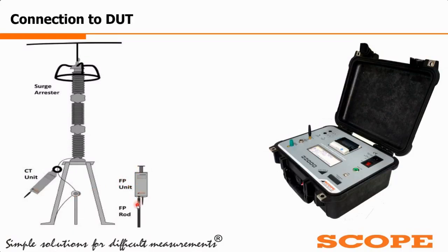The field probe unit with the FRP rod is supplied by default with the FRP rod, and as per your ordering, whether it is for 400 kV, 220 kV or 765 kV, we give the appropriate length of rod. But still, this field probe top must not be taken at any condition beyond the LA base. This is a very important precaution anybody must take during the test. Otherwise, due to the presence of the live line, and the field probe unit having a metallic structure, there could be a flashover between them, and though the FRP rod will save the person, the instrument can get damaged.